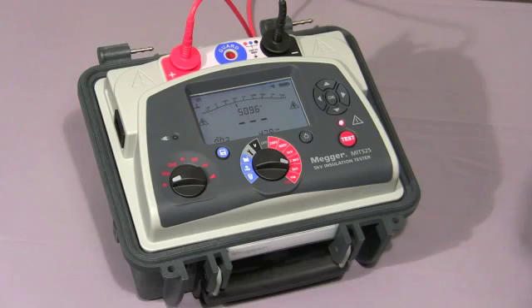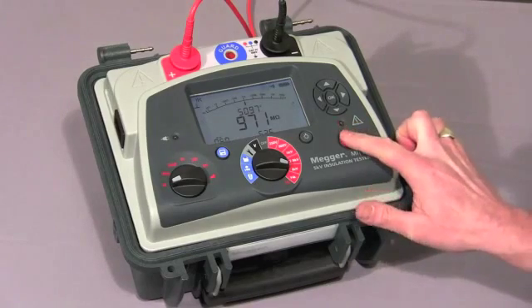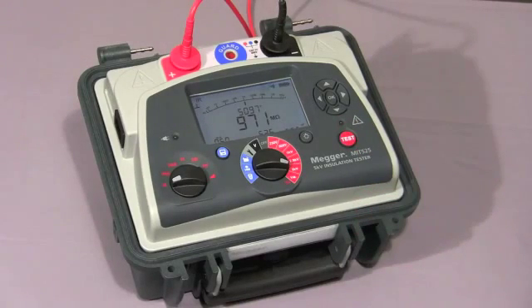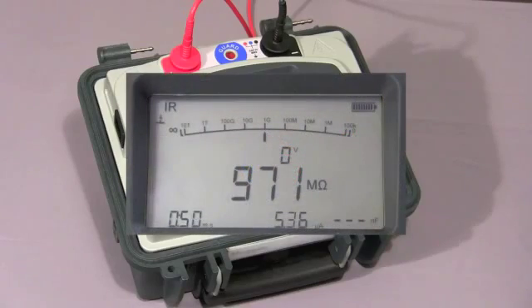That's to prevent accidental operation. You'll notice on the display the instrument is indicating the test voltage. Now we have the IR value in megohms. In the bottom left hand corner you'll note the timer, and also to the right of that we have the leakage current measurement. To terminate the test, you press the test button again. At this point the instrument will discharge any capacitance on the test piece, and then the display holds the measurement.